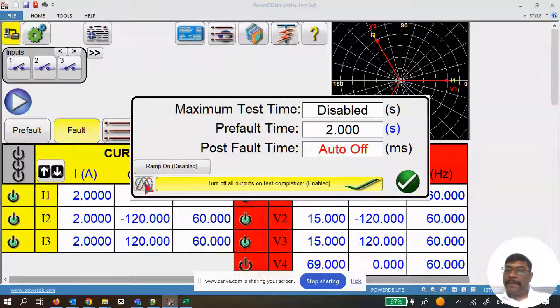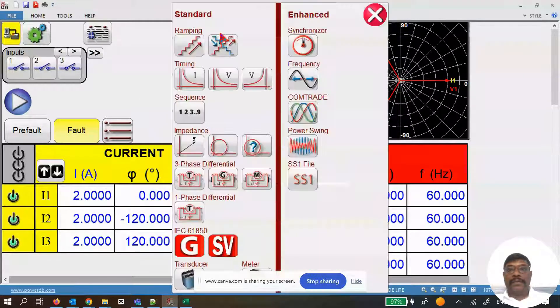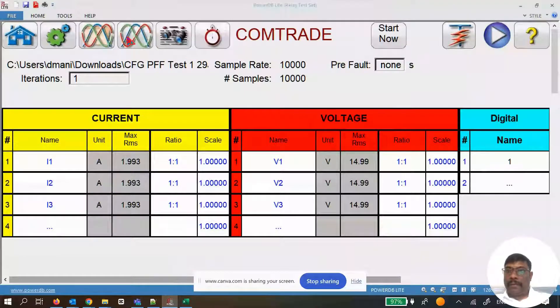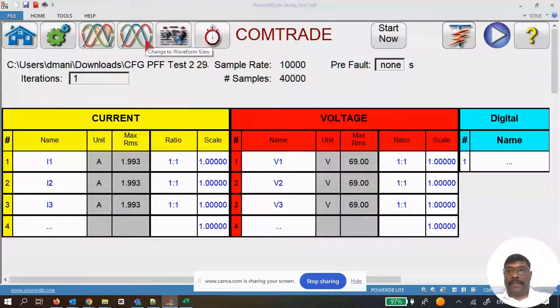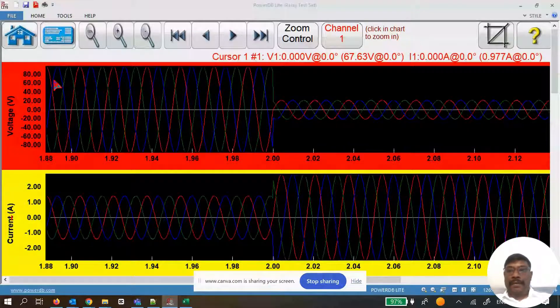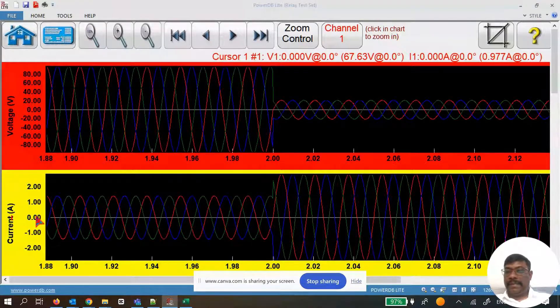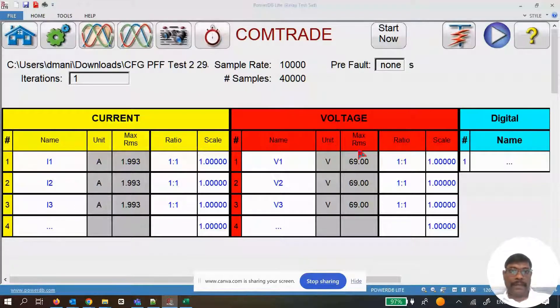I go to the export screen, press the comtrade export button, name it 'test two', save and close. Then go to the Tools menu, select Comtrade, click 'Open Comtrade File', find the file location, and open the CFG file. It generates the waveform automatically. Expanding the waveforms, you can see the default 69 voltage in RMS, the pre-fault at 1 amp, the fault at 2 amps, and after two seconds the comtrade fault segment is clearly visible.